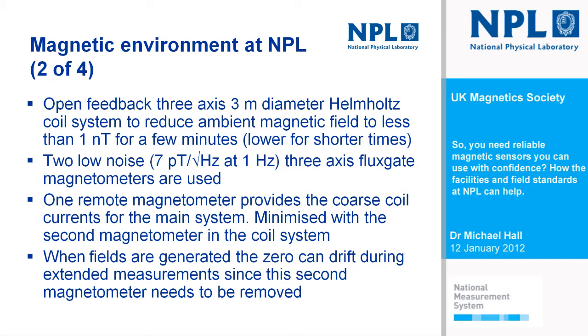And these points here, the last bullet point, they're just summarising that we can have this drift during extended measurements, and extended there meaning maybe 5 to 10 minutes. At the end of those measurements we would then put our 3-axis fluxgate back into the system and measure what the field was, and if it had drifted too much it would be necessary to repeat. So that is a weakness which we can overcome.